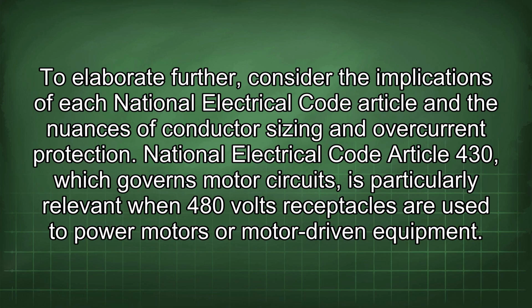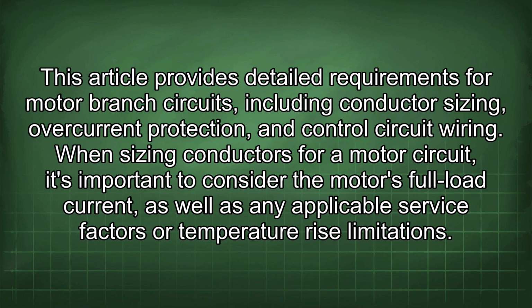To elaborate further, consider the implications of each National Electrical Code article and the nuances of conductor sizing and overcurrent protection. National Electrical Code Article 430, which governs motor circuits, is particularly relevant when 480 volts receptacles are used to power motors or motor-driven equipment. This article provides detailed requirements for motor branch circuits, including conductor sizing, overcurrent protection, and control circuit wiring. When sizing conductors for a motor circuit, it's important to consider the motor's full load current, as well as any applicable service factors or temperature rise limitations.